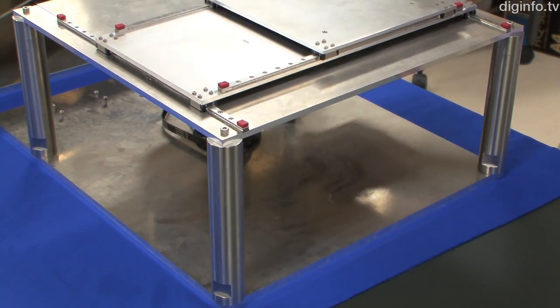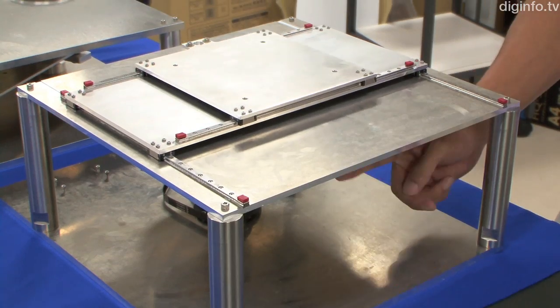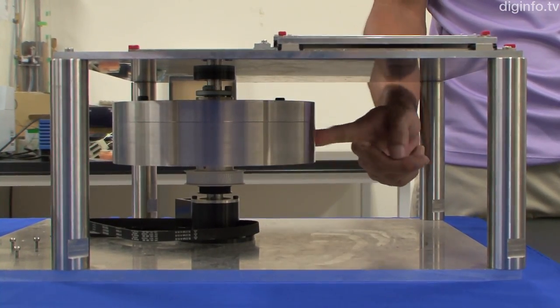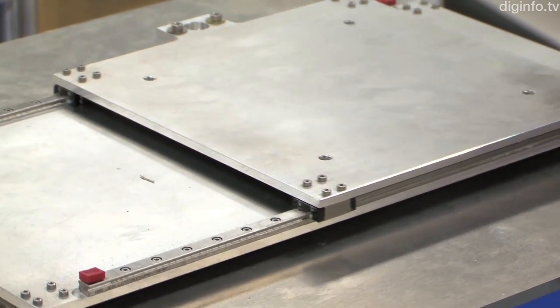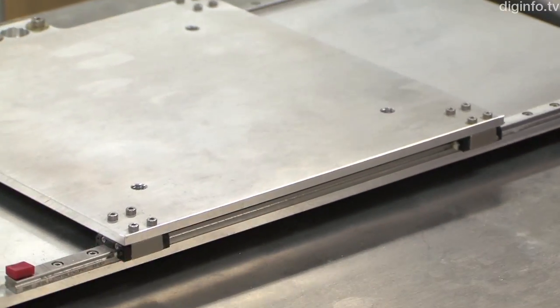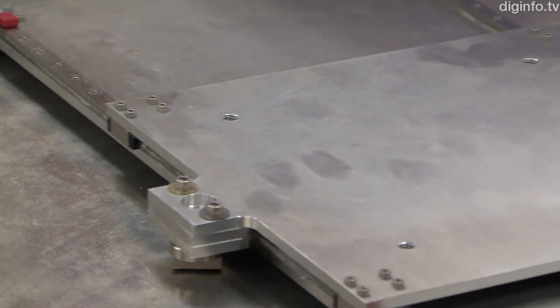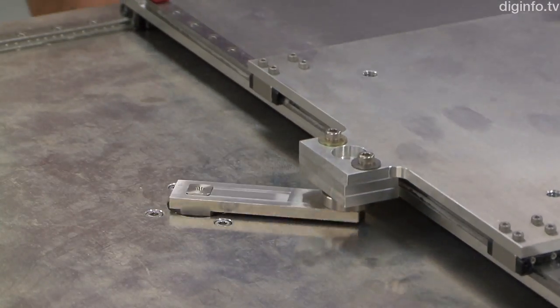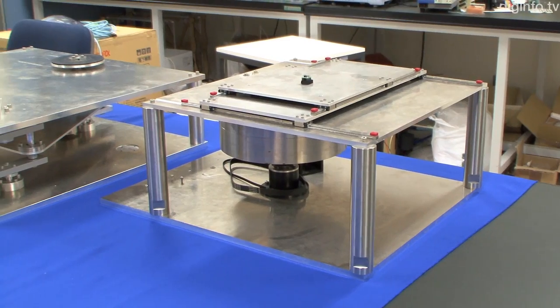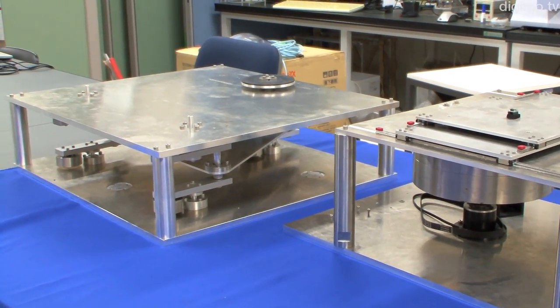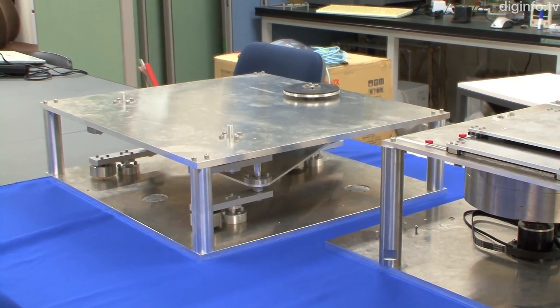The first thing the group did was rotate an XY table around an axis. But with an XY table where each part moves separately, the force required varies during the rotation. That's because when the two parts move at the same time, the required torque is increased compared to when only one part moves. After looking for a way to rotate the table while maintaining the sensor attitude, the group developed a device to calibrate acceleration sensors using parallel links.